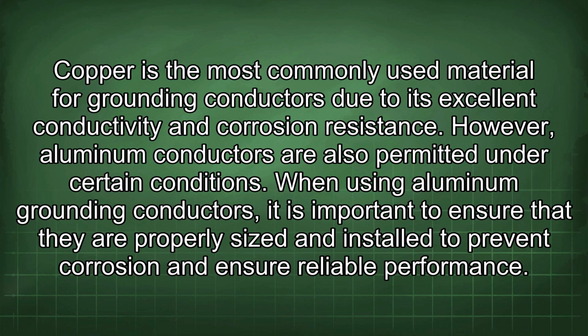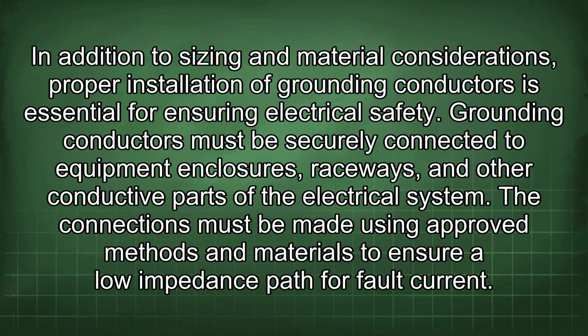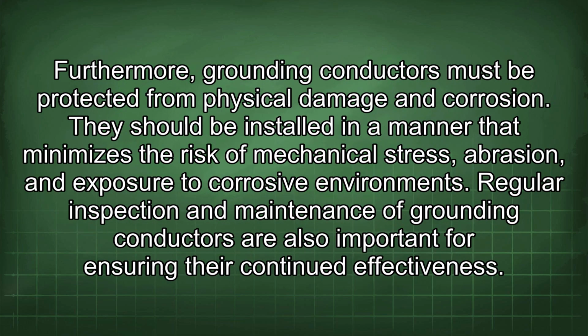and ensure reliable performance. In addition to sizing and material considerations, proper installation of grounding conductors is essential for ensuring electrical safety. Grounding conductors must be securely connected to equipment enclosures, raceways, and other conductive parts of the electrical system. The connections must be made using approved methods and materials to ensure a low impedance path for fault current. Furthermore, grounding conductors must be protected from physical damage and corrosion. They should be installed in a manner that minimizes the risk of mechanical stress, abrasion, and exposure to corrosive environments.